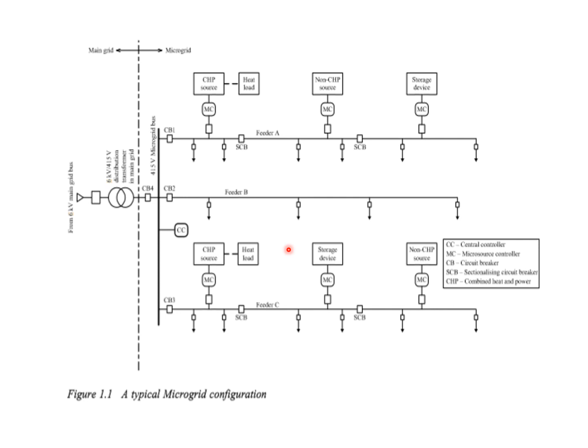The microgrid is operated in two modes, grid connected and standalone. In grid connected mode, the microgrid remains connected to the main grid either totally or partially and imports or exports power from or to the main grid. In case of any disturbance in the main grid, the microgrid switches over to standalone mode while still feeding power to the priority loads. This can be achieved by either disconnecting the entire microgrid by opening circuit breaker CB4 or disconnecting feeders A and C by opening circuit breakers CB1 or CB3.